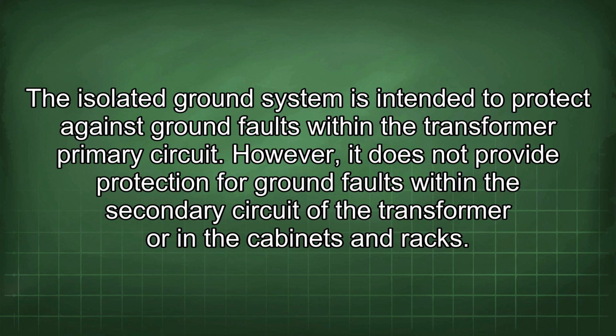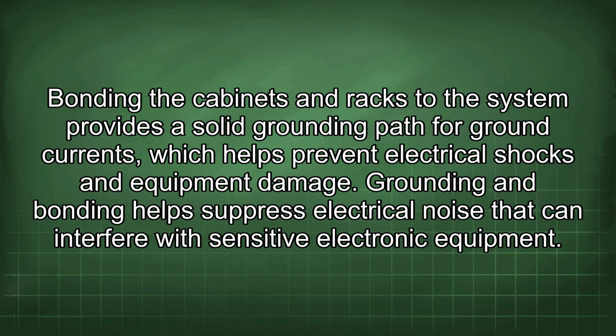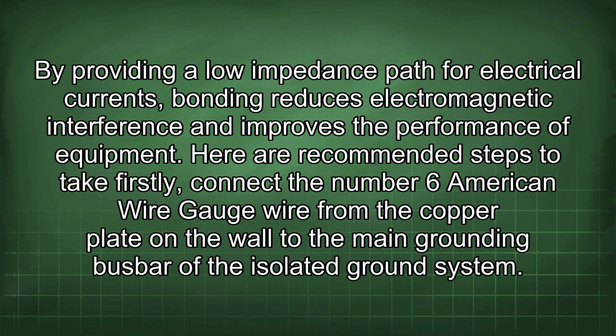However, it does not provide protection for ground faults within the secondary circuit of the transformer or in the cabinets and racks. Bonding the cabinets and racks to the system provides a solid grounding path for ground currents, which helps prevent electrical shocks and equipment damage. Grounding and bonding help suppress electrical noise that can interfere with sensitive electronic equipment. By providing a low impedance path for electrical currents, bonding reduces electromagnetic interference and improves the performance of equipment.